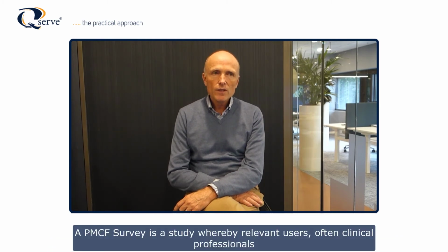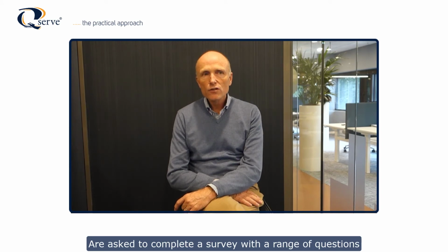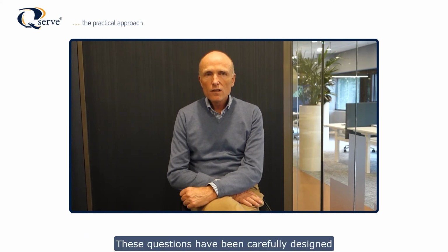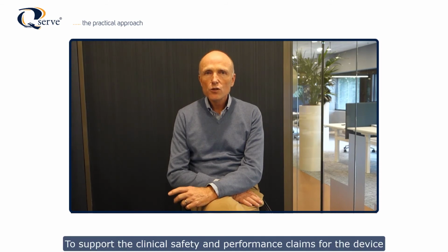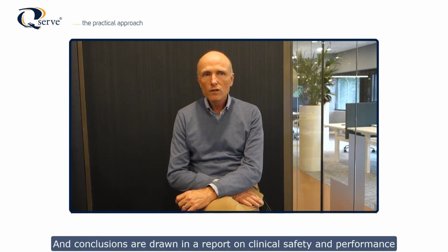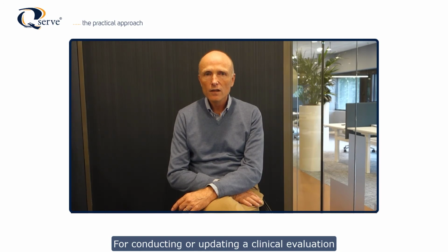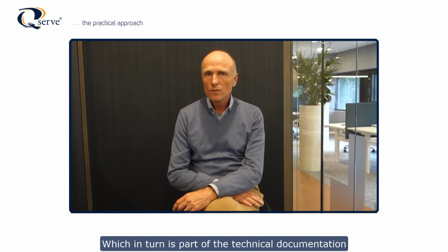A PMCF survey is a study whereby relevant users, often clinical professionals, are asked to complete a survey with a range of questions. These questions have been carefully designed to support the clinical safety and performance claims for the device. The responses to these questions form the clinical data, which are gathered and analyzed, and conclusions are drawn in a report on clinical safety and performance. This report then forms the input, in addition to a literature search, for conducting and updating a clinical evaluation, which in turn is part of the technical documentation.